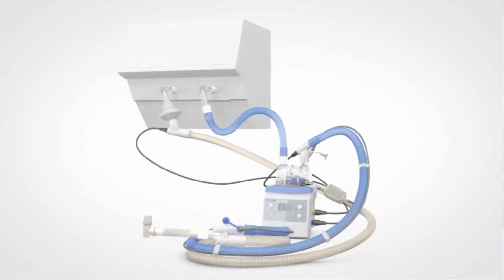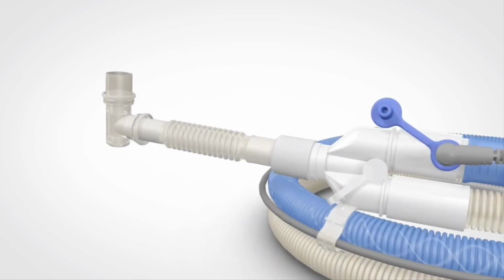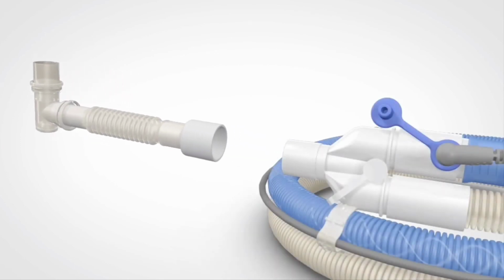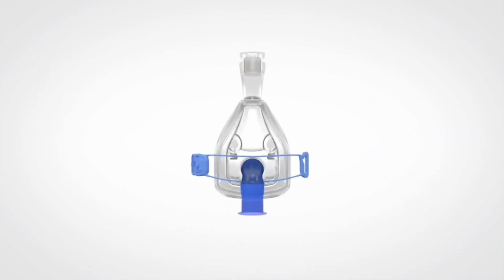The same Fisher & Paykel Healthcare invasive breathing circuit can be used to wean from invasive to non-invasive ventilation. This is achieved by adding a non-vented, non-invasive mask. If using an existing breathing circuit, disconnect the Y-piece from the catheter mount. Fit the non-invasive mask to the patient according to the instructions provided with the mask. Connect the mask to the Y-piece on the end of the breathing circuit.